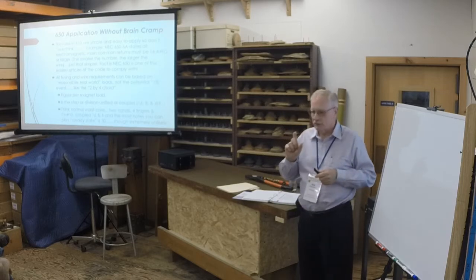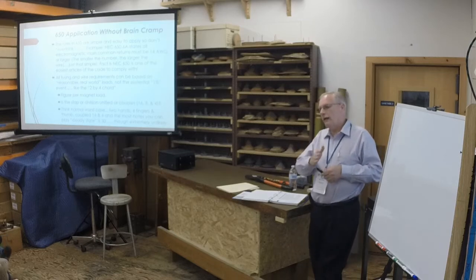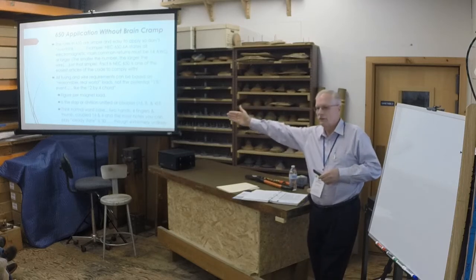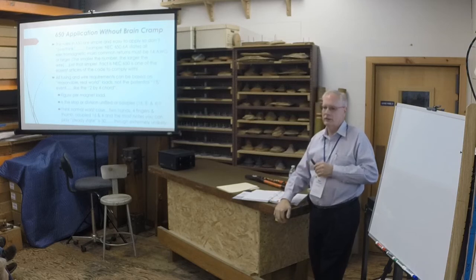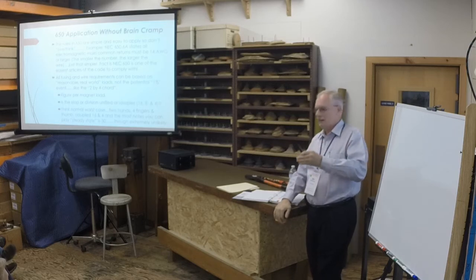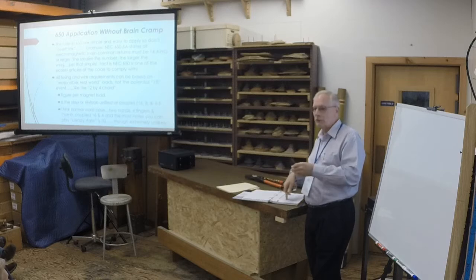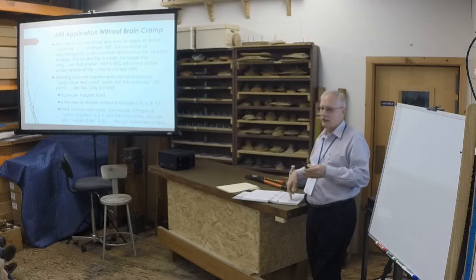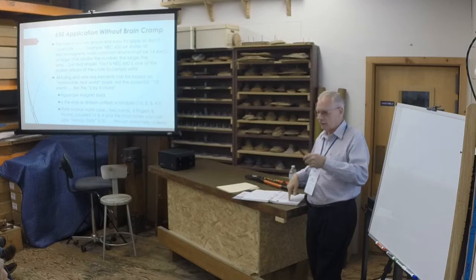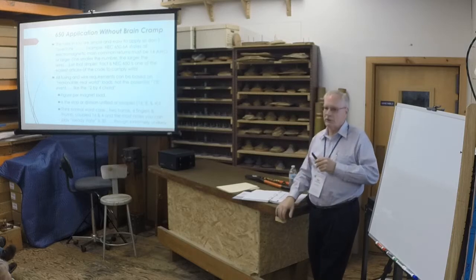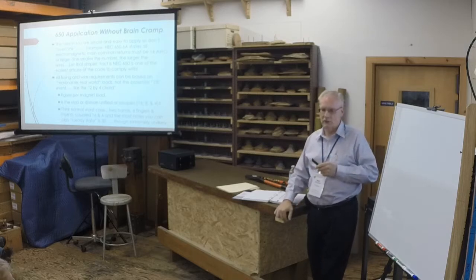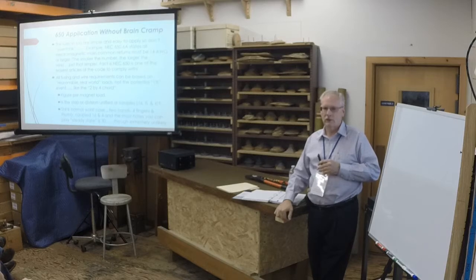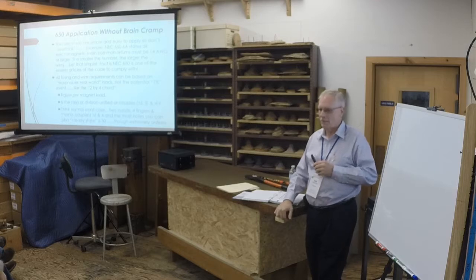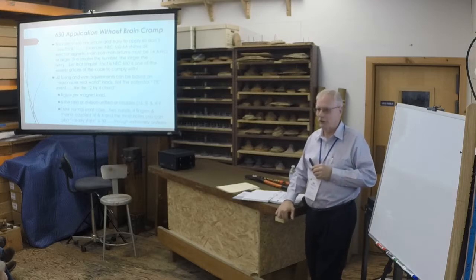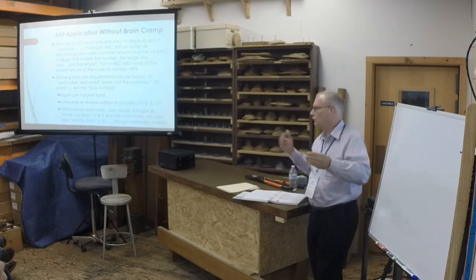And there's the ticket: everything from 20 gauge and smaller, the maximum fusing is 6 amps. Now, on your spare time when you have nothing to do, dig up the references I make in my documents and run some of these numbers through some calculators, and you'll sit there and say, how on God's green earth is 24 gauge applicable to 6 amps? For all practical purposes, it really isn't. Again, this is one of these contradictions.